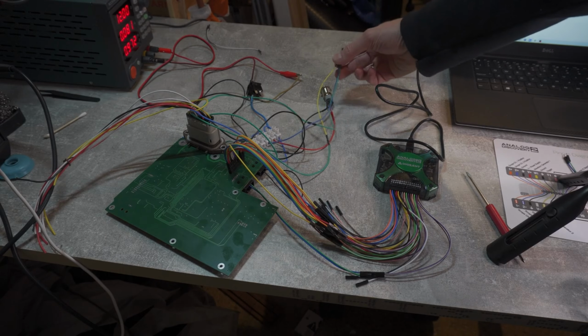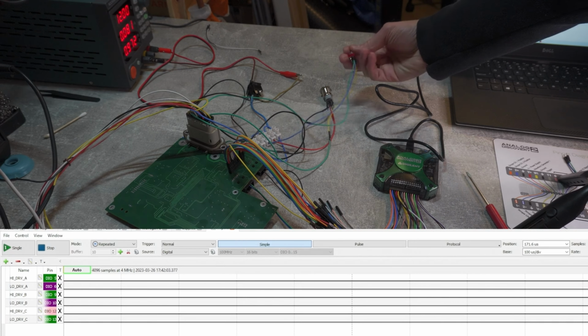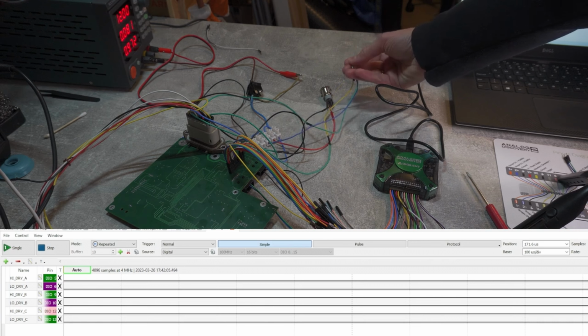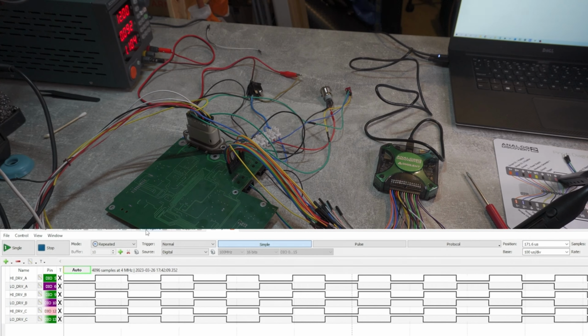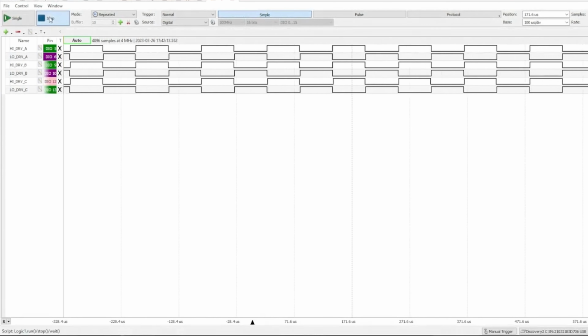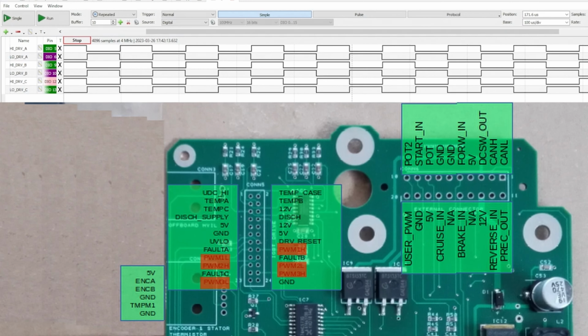So first, to test the inverter, I need to run it in the manual mode and measure the PWM signal produced by the processor. I'm now switching the inverter into forward mode, and this should start PWM signals for all 3 phases. And here we go, we can observe PWM signals, high and low, for all 3 of the phases we have.